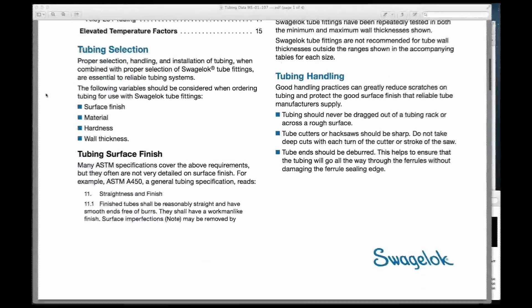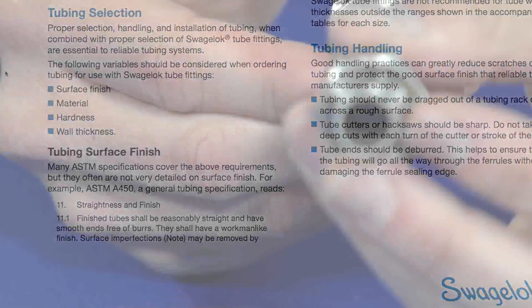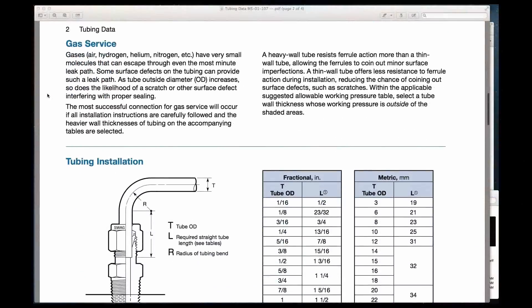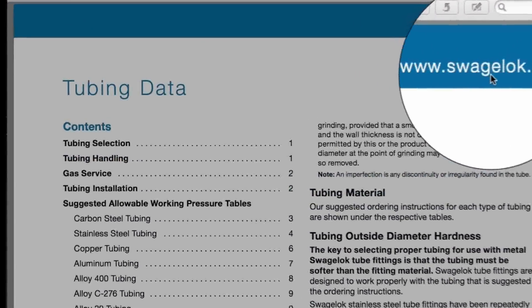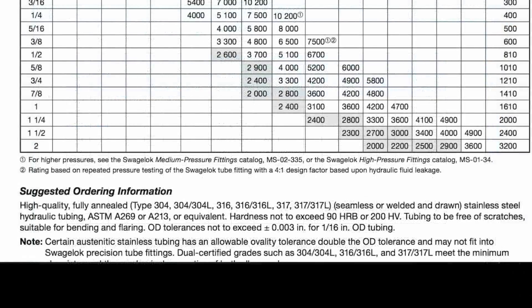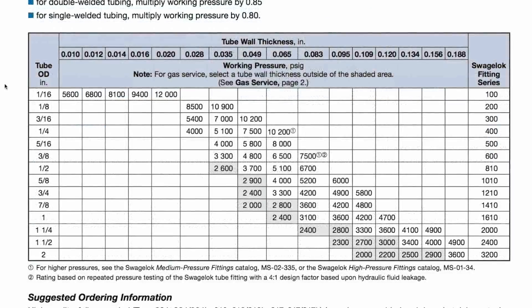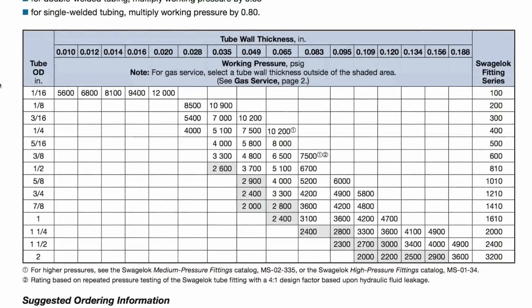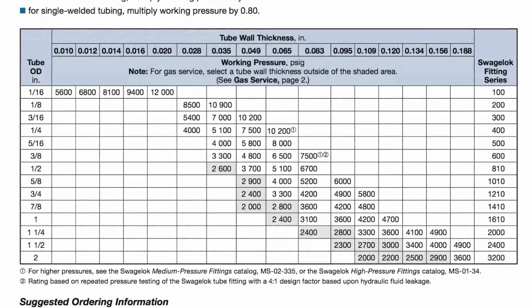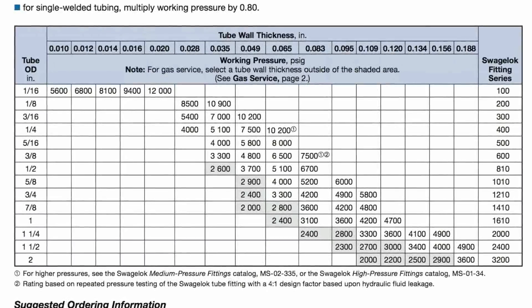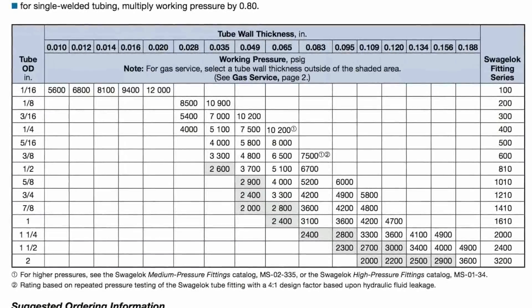Surface finish, material, hardness, wall thickness. Details on these variables can be found in Swagelok's publication entitled Tubing Data. In it, you will find suggested allowable working pressure tables and suggested ordering information for tubing to be used with Swagelok tube fittings. The tables have the outside diameter of the tubing on the vertical axis and the tube wall thickness on the horizontal axis. Tubing combinations without working pressure ratings are not recommended for use with Swagelok tube fittings.